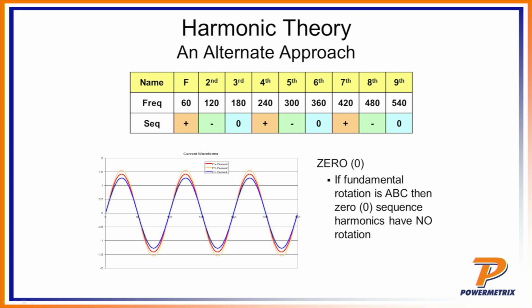to burn up. One story that I heard at a meter school once, that there was a customer out in Phoenix, Arizona. It was a golf course, and they had recently switched over from using gasoline go-karts to electric go-karts. Unbeknownst to them, the battery charging system had a real problem with these 0th level harmonics. And so as such, all these harmonics summed up together, all that current was being dumped back into the ground conductor. It basically overloaded that ground conductor, caught the clubhouse on fire and burned it down, just because they didn't realize that there was so much harmonic energy being dumped into the system. Real story.